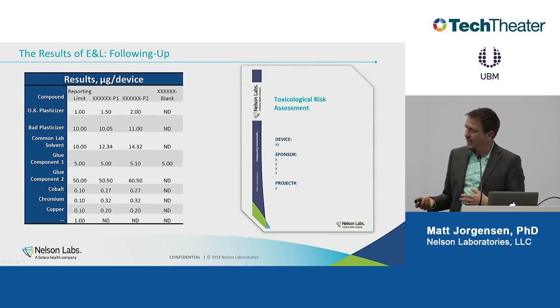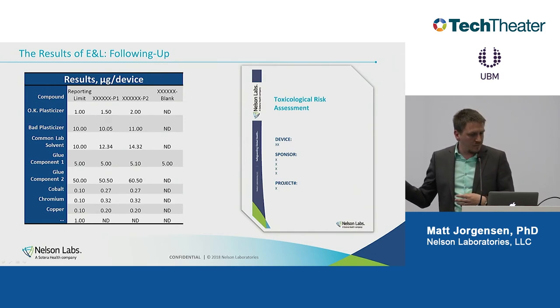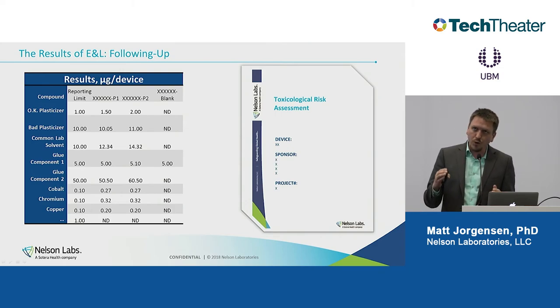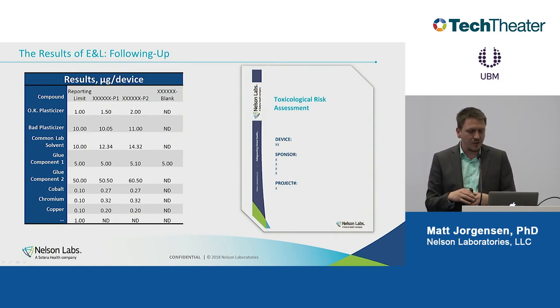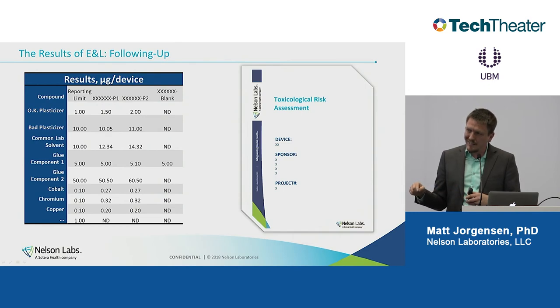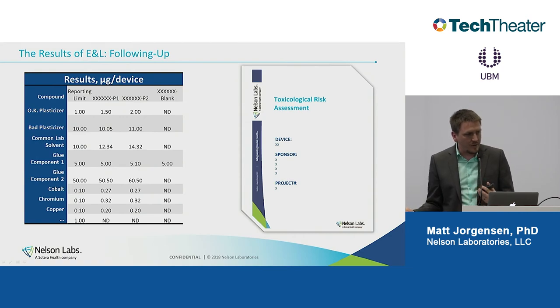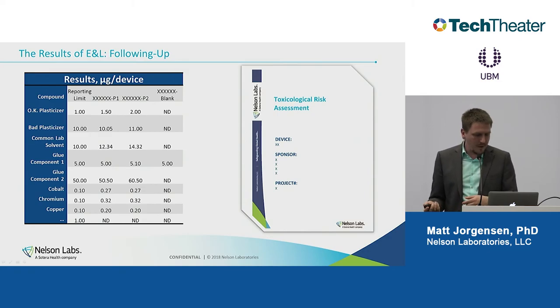Another area where things are changing: once you have these chemistry results, they should be interpreted through some toxicological risk assessment. The details about what that risk assessment should include, and to which sensitivity the analysis needs to go, is something that shifts all the time. So the new ISO 10993-18 will rely a lot more heavily on this concept of an analytical evaluation threshold that comes into play with the toxicology. So that's in the pipeline.